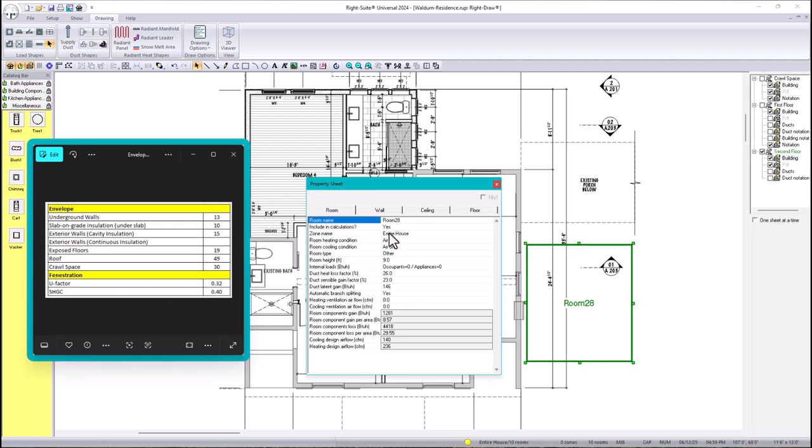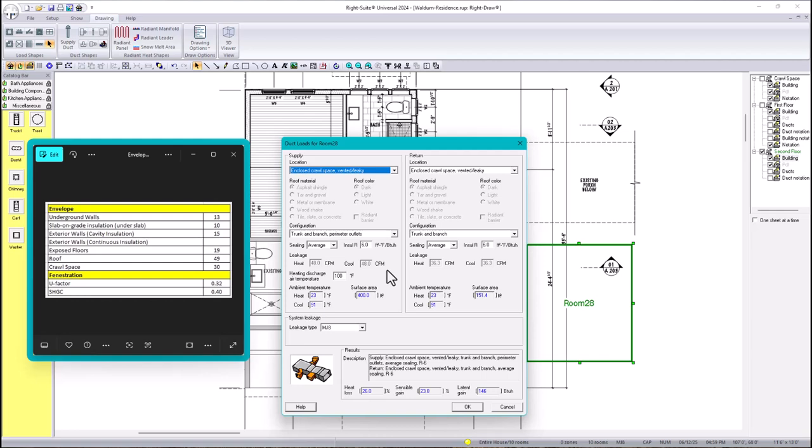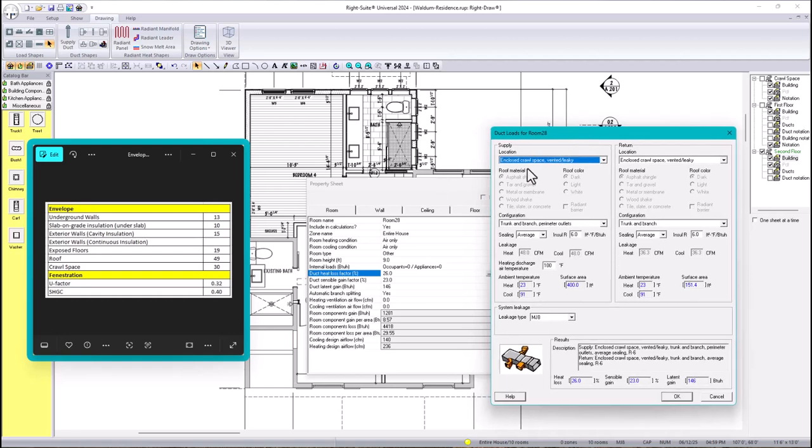in the room itself, number one, what I'm gonna do is the heating conditioning, air only, that's right, but the duct heat loss. So for the duct heat loss, this is a very interesting topic because this means where are you gonna run your ductwork. So as you can see in here in the second floor, you are not going to run your ductwork in the attic space because if you check on the architectural drawings, there is no attic. There is no attic. So how do you see that actually in the drawings?